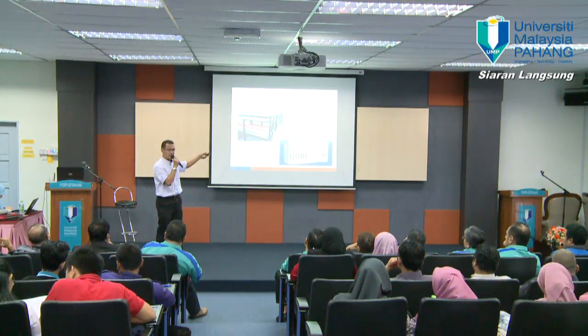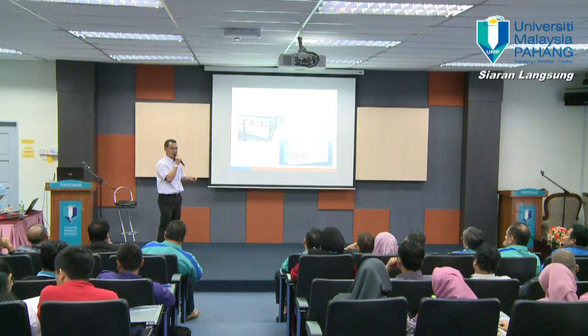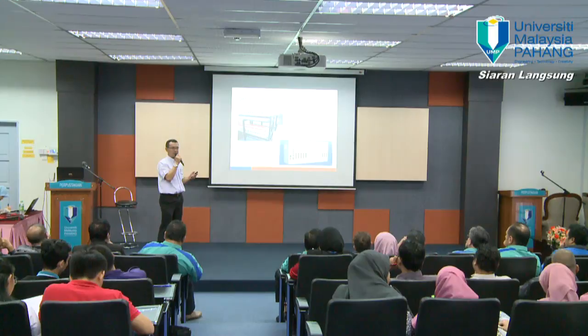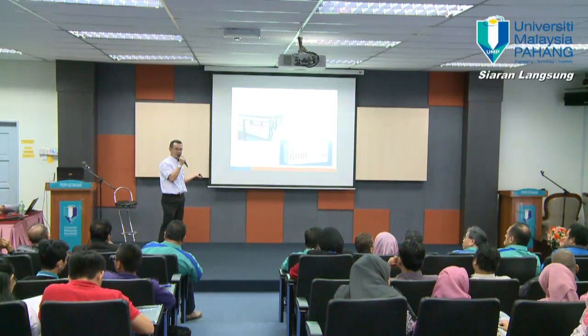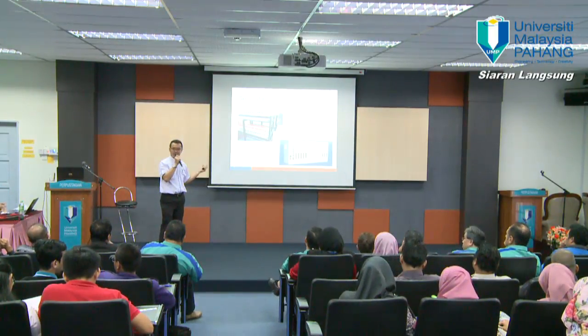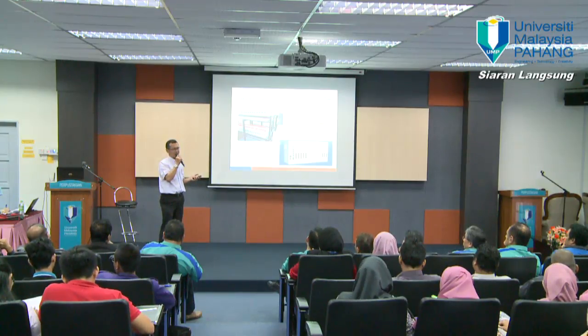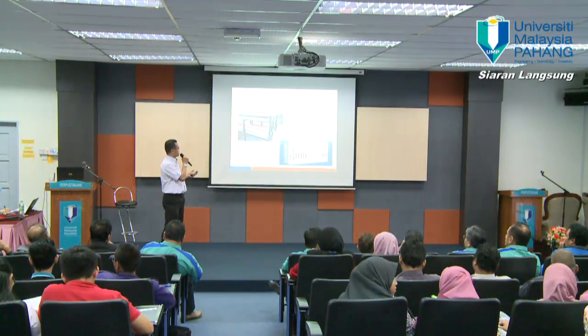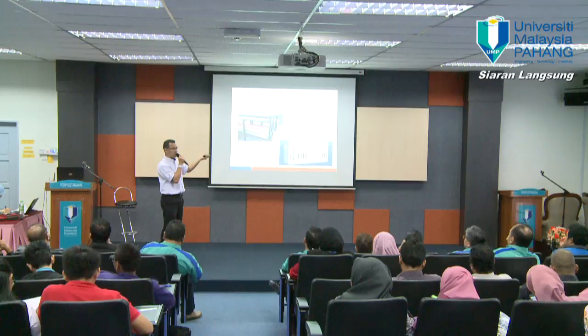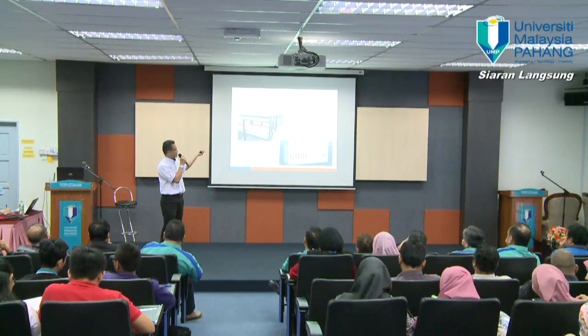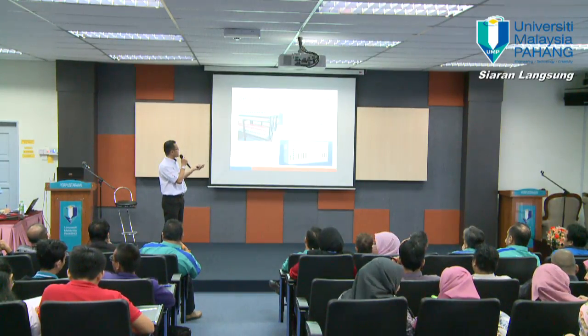Normally we use normal charger. This is for standby. In case of interruption of the AC supply, the battery will take over about 4 to 5 hours. All the secondary use DC. No wonder we need the battery.